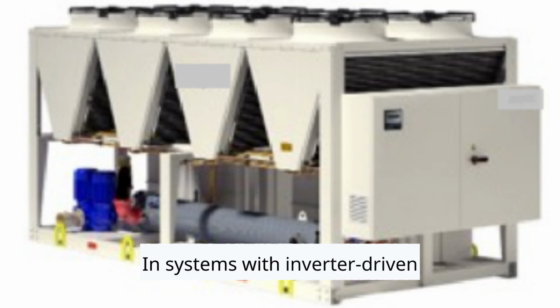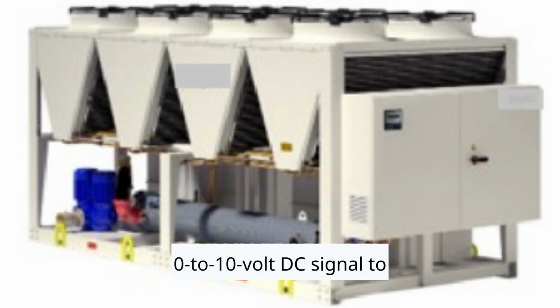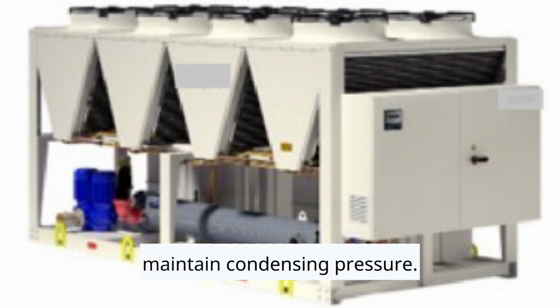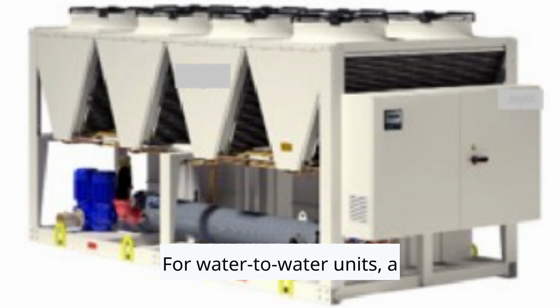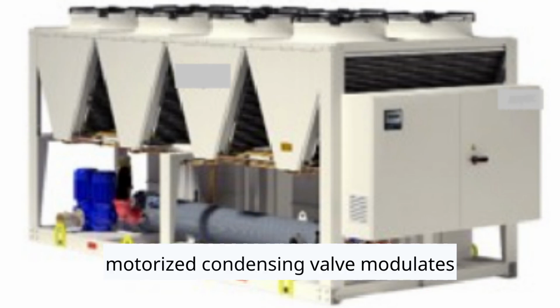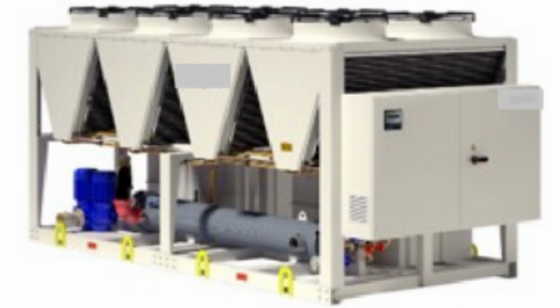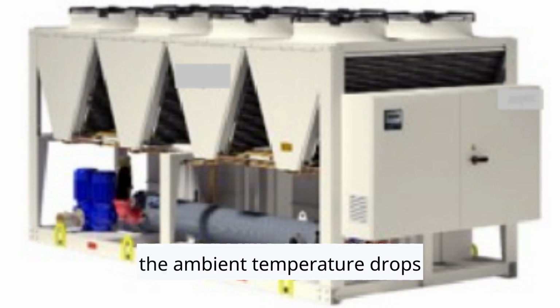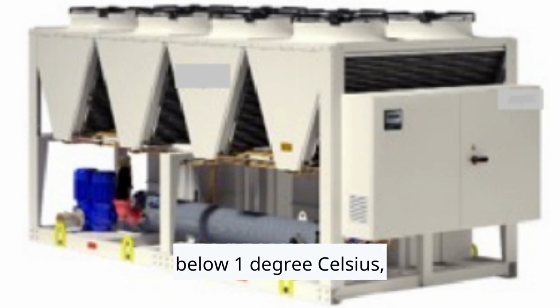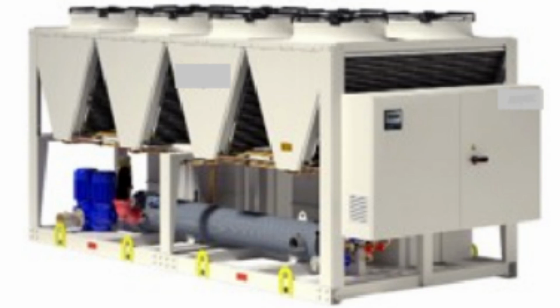In systems with inverter-driven fans, fan speed is automatically adjusted using a 0 to 10 volt DC signal to maintain condensing pressure. For water-to-water units, a motorized condensing valve modulates in the same way to stabilize system head pressure. In colder climates, when the ambient temperature drops below 1 degree Celsius, the condenser fans are programmed to run for 30 seconds every 2 hours. This simple routine helps prevent fan shaft freezing during long periods of inactivity.